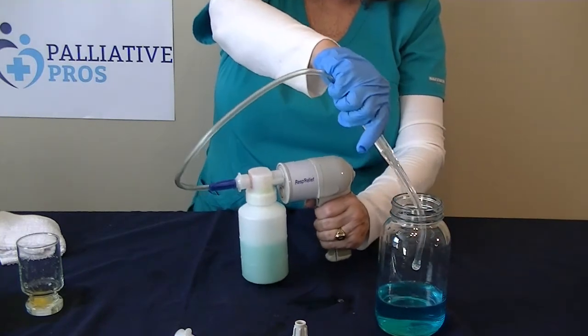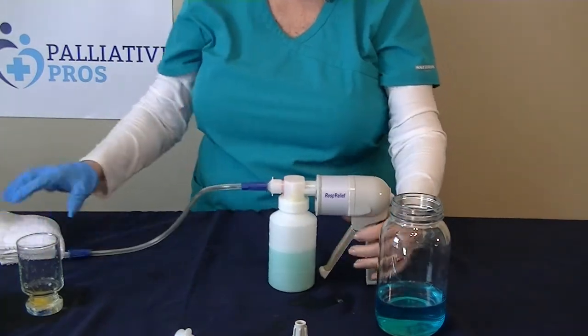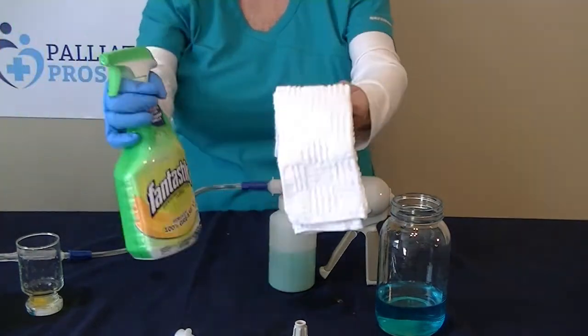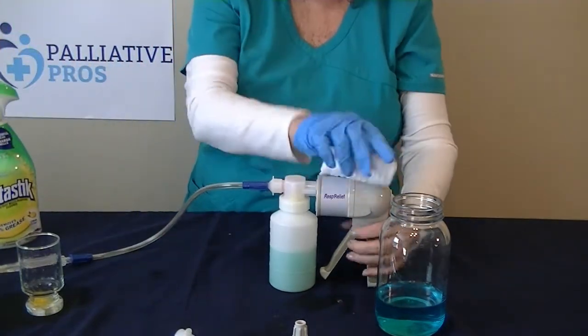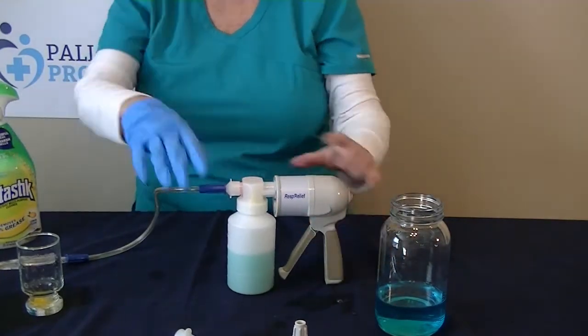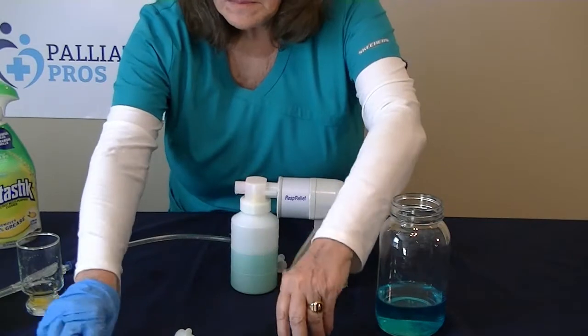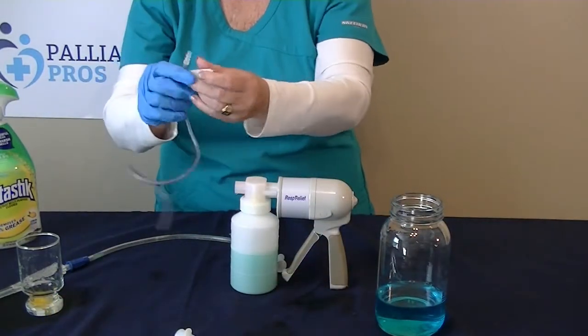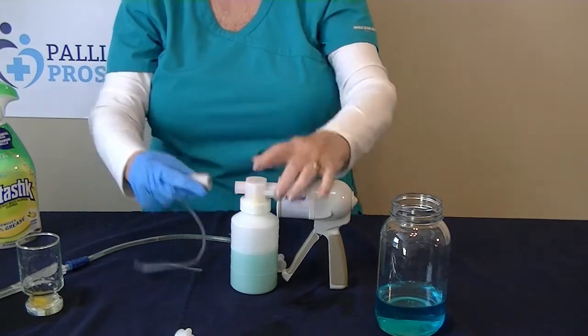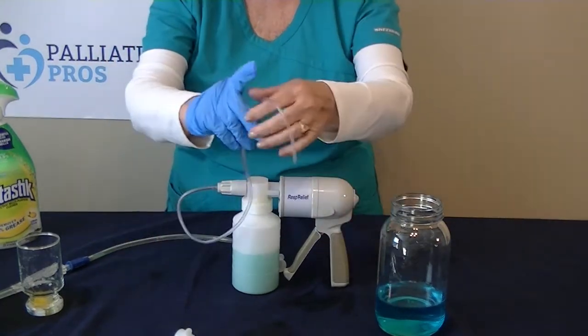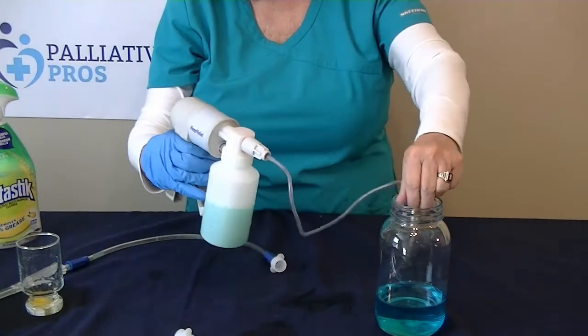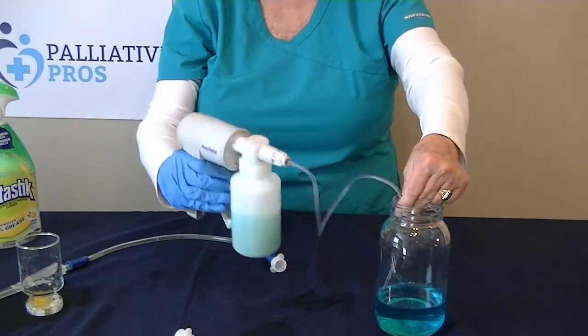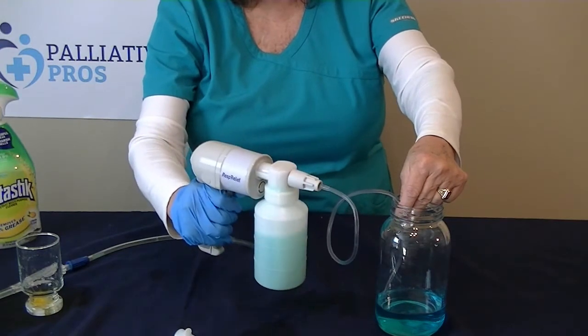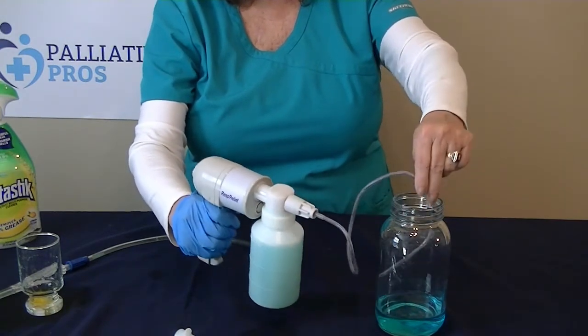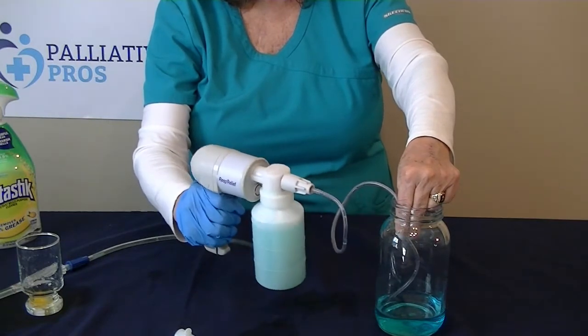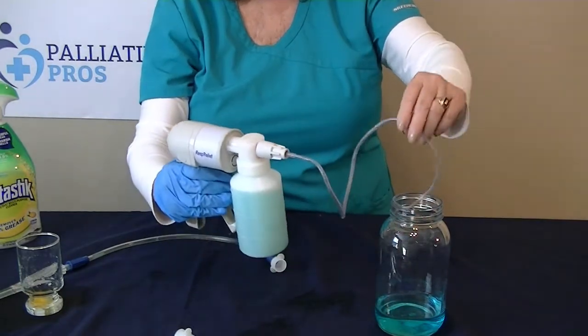When it comes time to clean the device, use a wipe with disinfectant, but never submerge the pump in water or other liquids. Just wipe it with a dry cloth and a disinfectant. If you do make a mistake and submerge the pump in a liquid, you should replace the pump. The pump and attachments are 100% disposable. It's designed for disposal after each use. Dispose in a manner that ensures body substance isolation and according to your organization's biohazard disposal protocol.